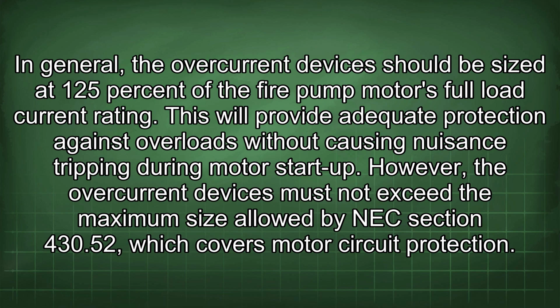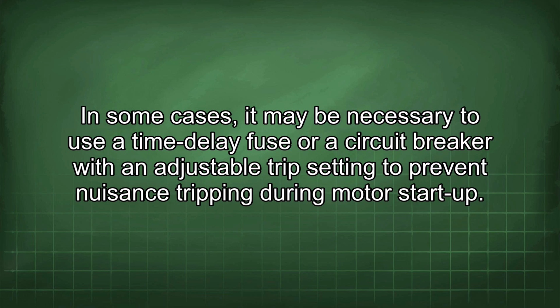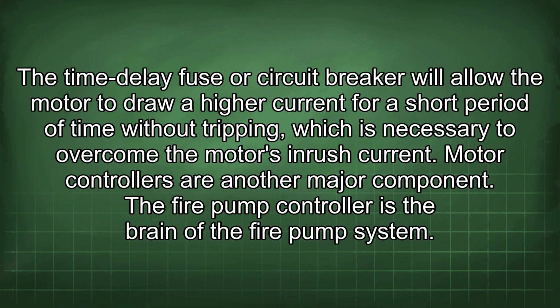However, the overcurrent devices must not exceed the maximum size allowed by NEC section 430.52, which covers motor circuit protection. In some cases, it may be necessary to use a time delay fuse or a circuit breaker with an adjustable trip setting to prevent nuisance tripping during motor startup. The time delay fuse or circuit breaker will allow the motor to draw a high current for a short period of time without tripping, which is necessary to overcome the motor's inrush current.